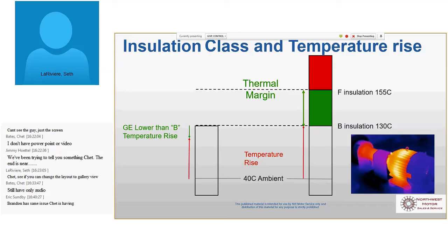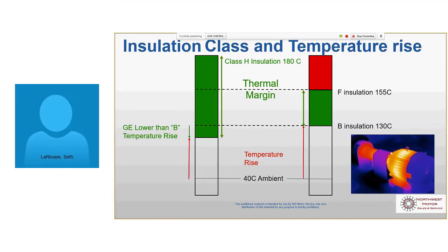So if I'm a motor manufacturer, the single most important thing I can do to ensure the life of my motor is to design it with a low temperature rise and a high temperature limit. And that's exactly what GE did on this one. So it's designed to run at a B, but it has a Class H limit. So this is all that's required by that specification, and then 25 degrees C on top of that. So between the two of these, this is 130, so it's going to operate at 130 up to 180. You've got 50 degrees now, so it's doubled the amount of thermal margin that the spec demands. So what that means in the real world is that motor runs cool, and like I said, heat is always the enemy. The cooler that motor runs, the longer it'll last. The grease lasts longer, the windings last longer.